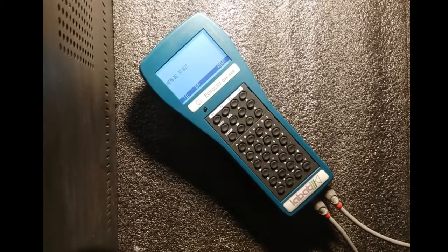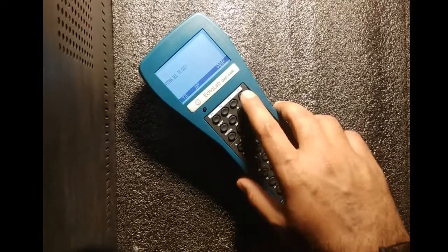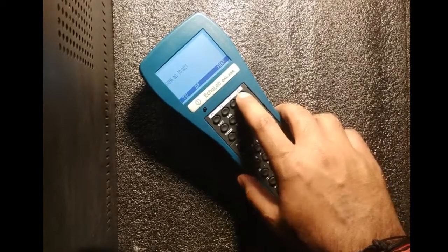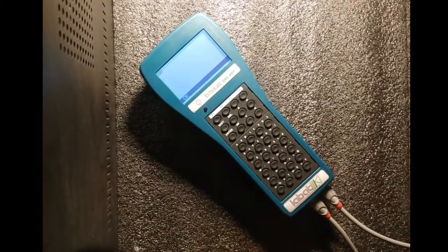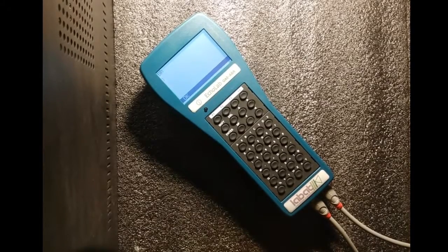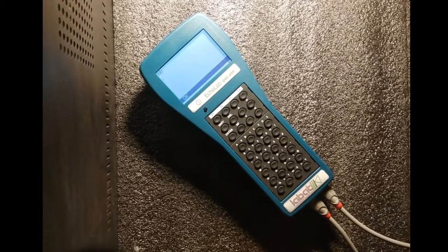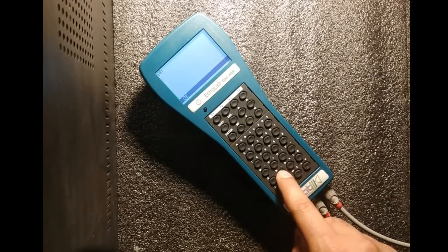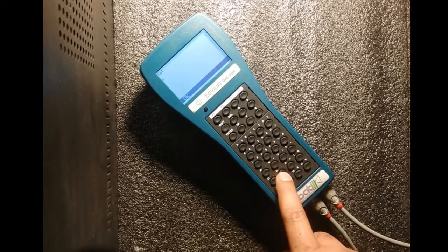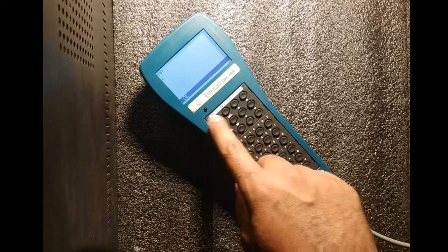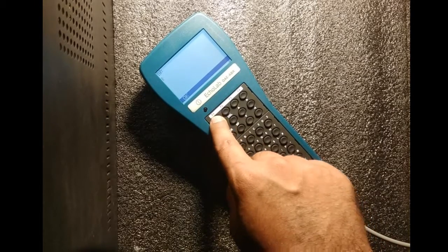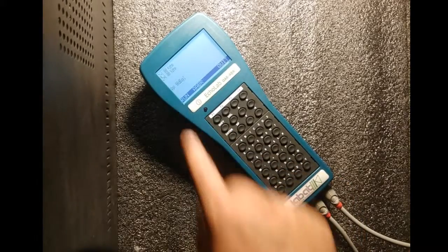Once you have made the connection of the electrodes on the patient, you will hit F4. It will ask which ear you want to put the probe in - that will be the testing ear. We are testing the right ear, so I am hitting R for right. You can hit L for left. After that, we will press F1. You can see the impedance is quite low.